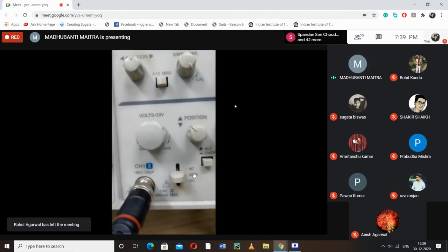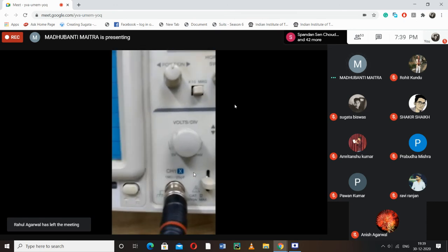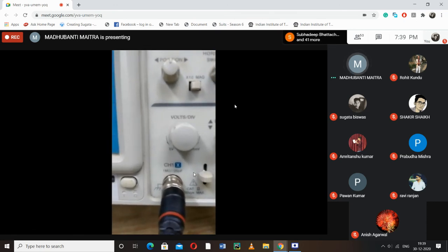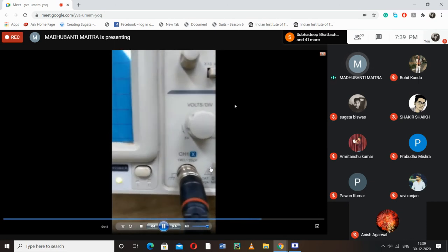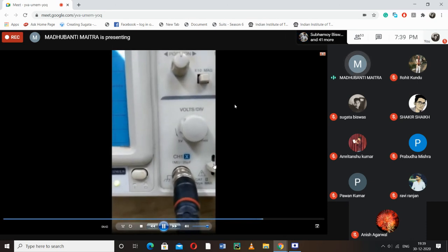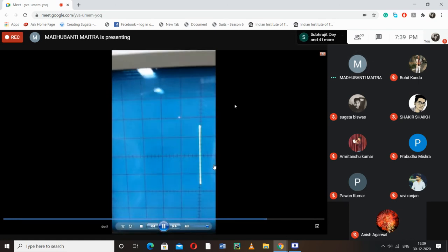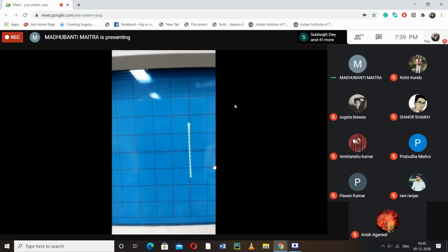If you have any query, please ask me, then I'll pause the video and I'll try to answer them. So when we are measuring the output, we are grounding the input signal. As I said, there are 3 positions. One is AC, DC, and ground. The middle one is ground.